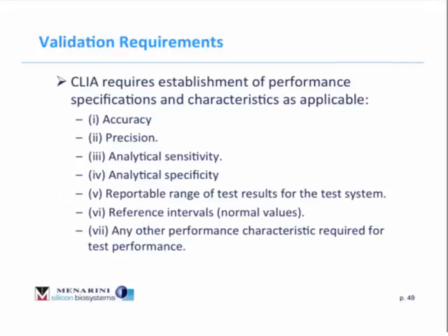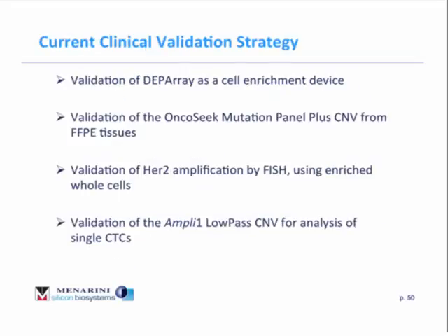So how are we validating this device? That's actually a very interesting question. If you look at the CLIA regs from '88, hard-coded into those regs are the requirements for accuracy, precision, sensitivity, specificity, reportable range, etc. And these are absolute requirements. So how do we do it?